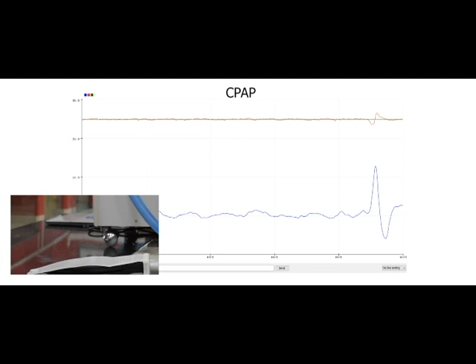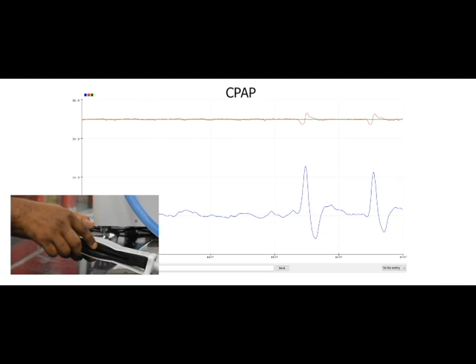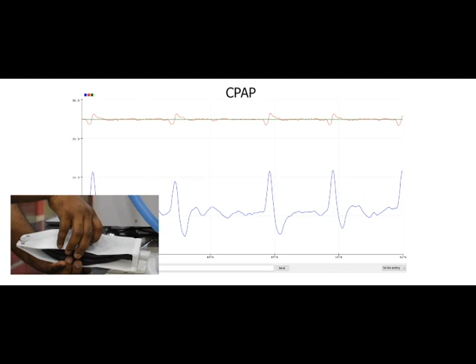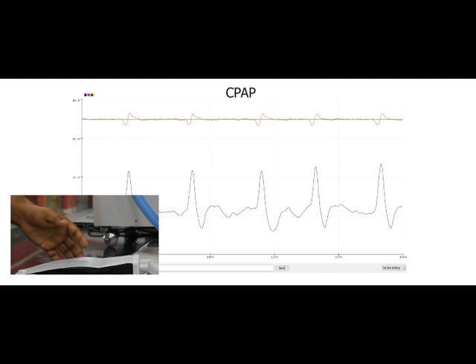I will first set the situation in my mechanical ventilator. Now you can see that the machine is developing a constant positive airway pressure in the lung, so the lung is a little inflated here. If I try to take my own breath, the machine should support that. The pressure setting is now at 25 centimeter of water column. Now I do the mechanical ventilation with patient triggering in CPAP mode. You can see the patient's breath is being supported at around 25 centimeter of water column. So this CPAP mode is also very, very important for COVID patients, which our mechanical ventilator PranVayu has achieved.